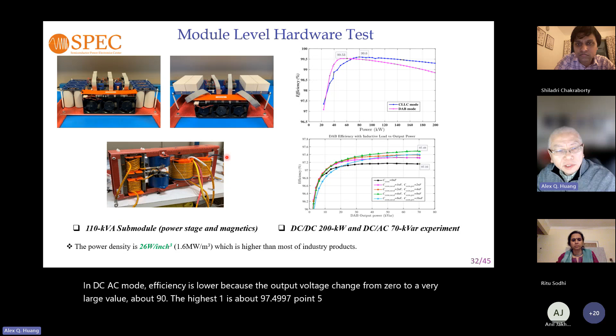So one of the key solutions here, of course, is the silicon carbide power module. In this case, we use a 1700 volt power module. And since it's a module, the footprint becomes bigger. One of the major issues is how to design a bus bar to connect all the devices together. So the typical solution is a laminated bus bar or printed circuit board-based bus bar.